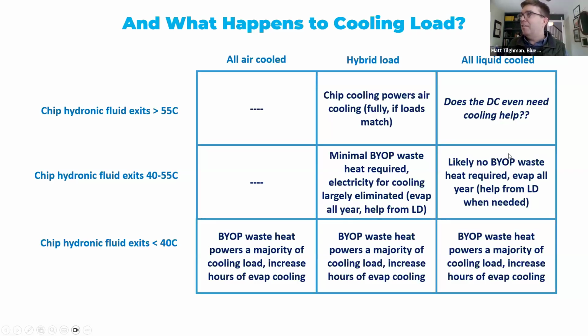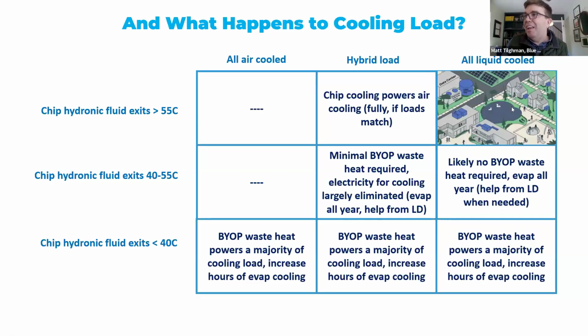But then kind of the one that made all of the air conditioners lose their valuation, and the one that had us dancing is the top right one, which is, okay, if we're shifting towards mostly liquid cooled, it'll never be all liquid cooled, but mostly liquid cooled, and the water's allowed to go in at 45 Celsius, where did the cooling load even go? Do these data centers even need help with air conditioning? And the answer is maybe not. And that's a really good thing for us.